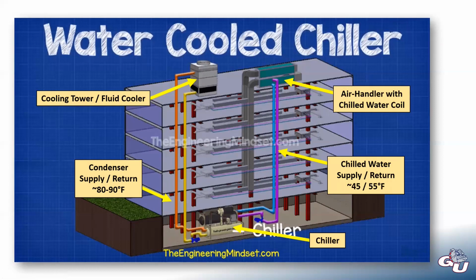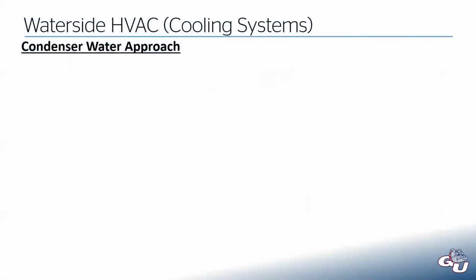This seems like a long way to go for your piping, going from the roof down to the basement, up to the roof again. That's probably not how most of these projects would be designed. More likely there'd be multiple air handlers throughout the building, maybe one air handler per floor or something like that. But fundamentally, that's how this system is configured. We're going to come back to this idea of approach, which we talked about quite a bit during the heat pump lecture.